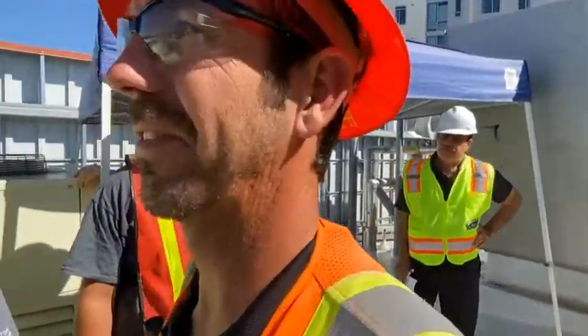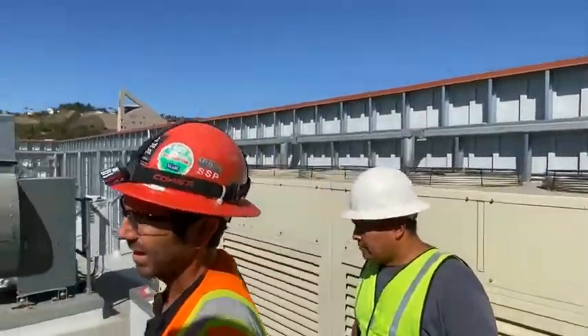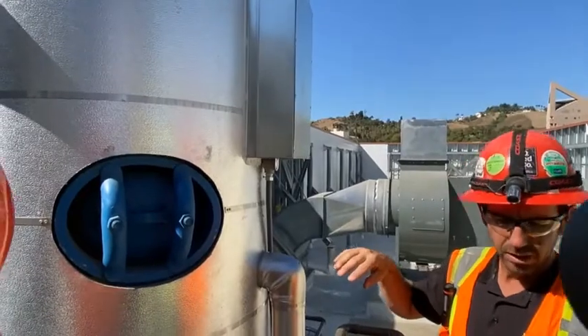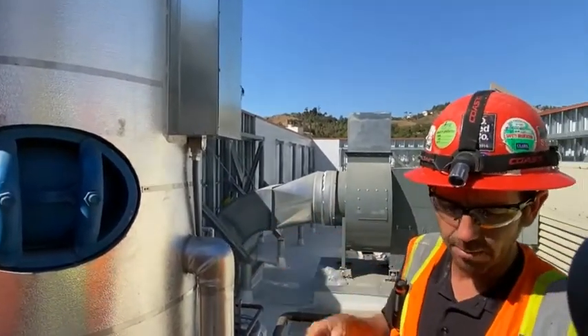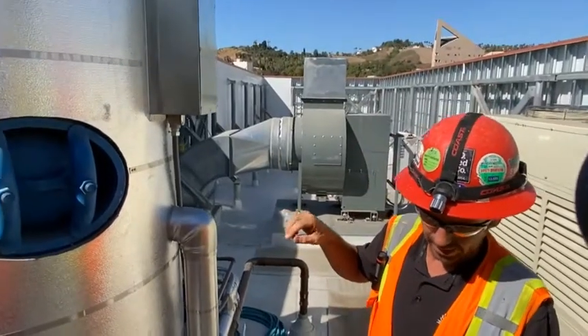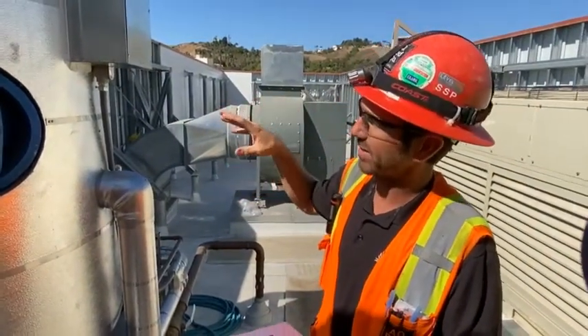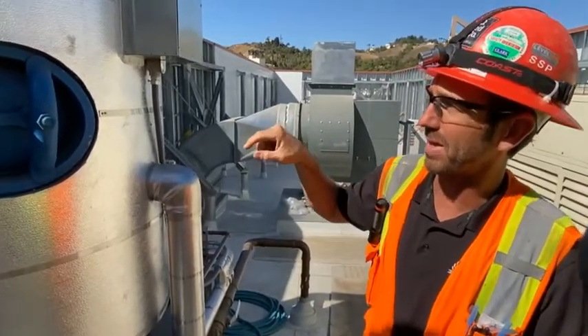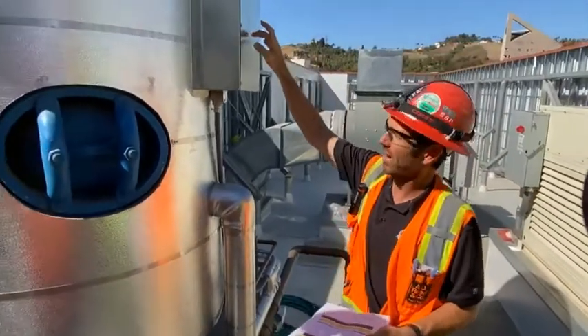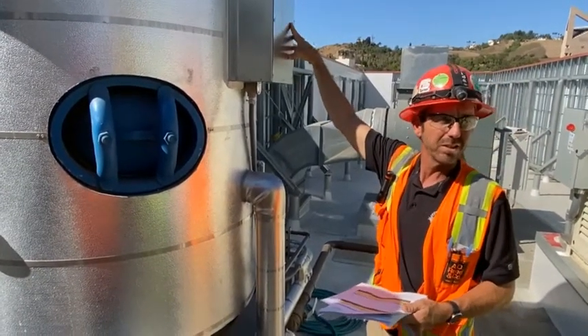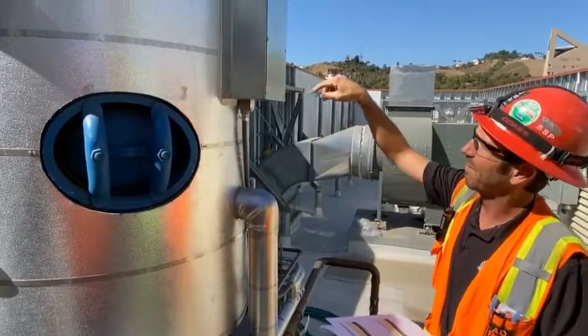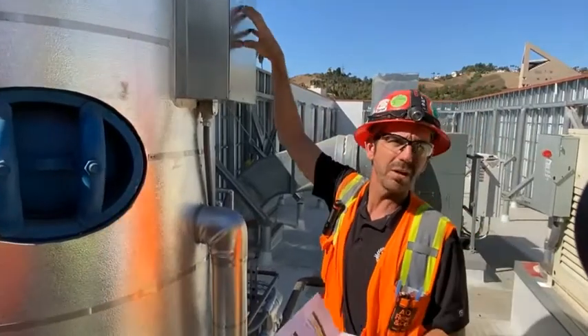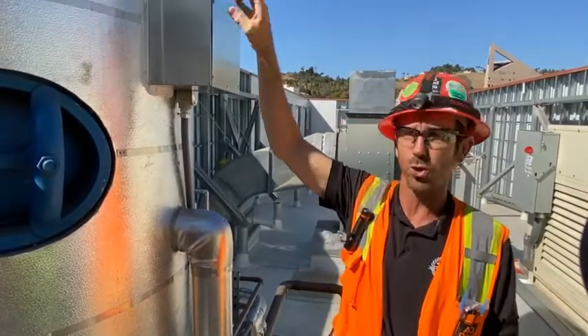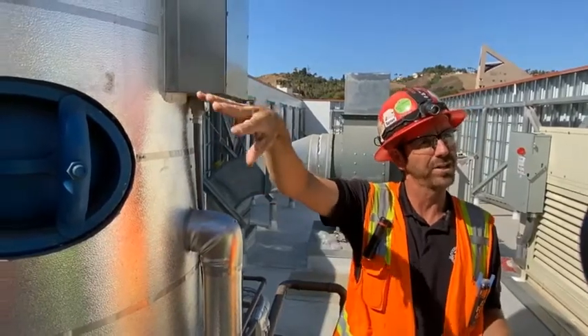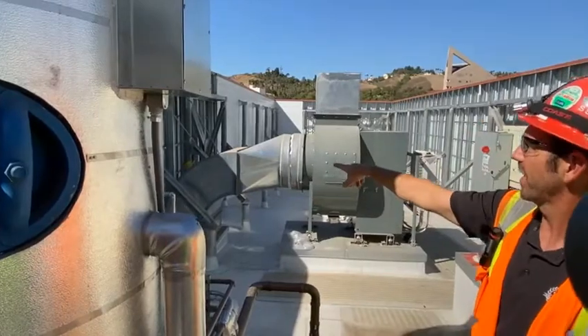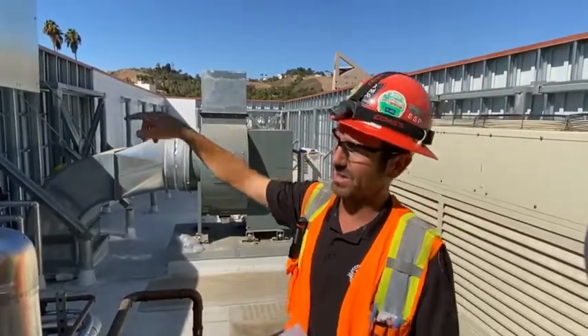Since we're up on this side of the roof, we'll jump into the storage tank here. Talked about it yesterday a little bit. To follow up on some maintenance procedures on this, the manufacturer recommends monthly that you check the pressure off the tank and make sure we're not over the manufacturer's recommended maximum pressure. Inside this cover right here is the manufacturer's nameplate. So to get that information, you can go in here. That's also where the aquastats are. There's two aquastats stacked on top of each other. Remember, the aquastats are controlling each individual pump. One aquastat for one water heater, one aquastat for the other, okay? Yesterday we saw the aquastats, and examples are over here on the circulation pumps.